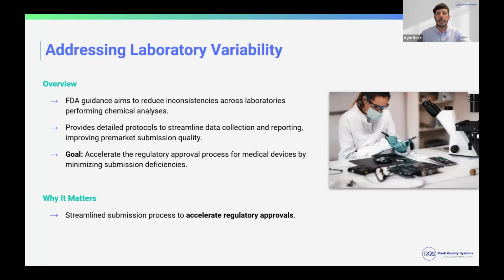Another thing that the guidance document discusses is laboratory variability. So making sure that we have consistency across different laboratories. So this is not only for the device manufacturers, the ones that will be going through the testing, but also the guidance applies to the labs that will be doing the testing. So make sure that they have detailed protocols to streamline data collection and reporting, and that they have validated methods for conducting this type of analytical testing.